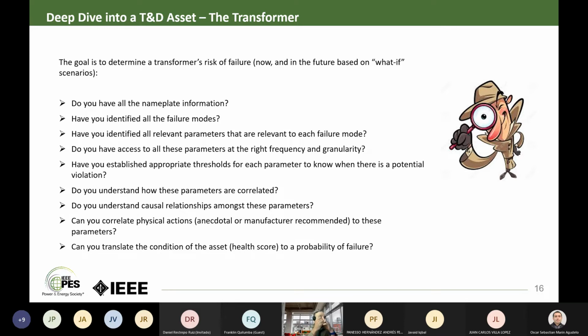Example here is, if I'm looking at dielectric failures, then I need to be looking at the oil, the quality of the oil, the moisture content, and so on. But the question is, how often do I need it? Do I need it every second? Do I need it every hour? Do I need it once in 6 months?